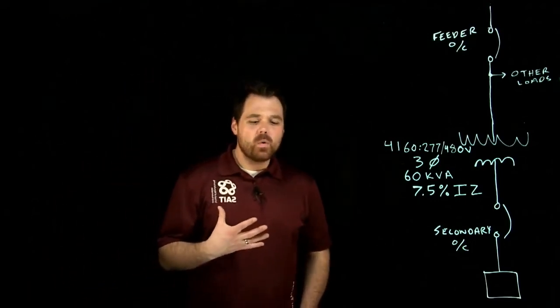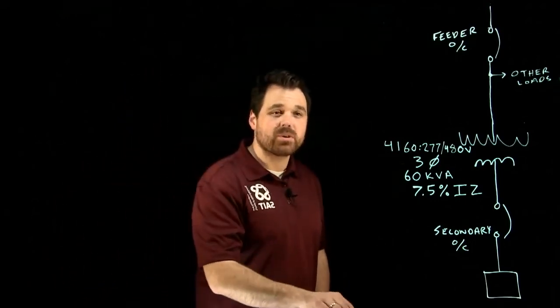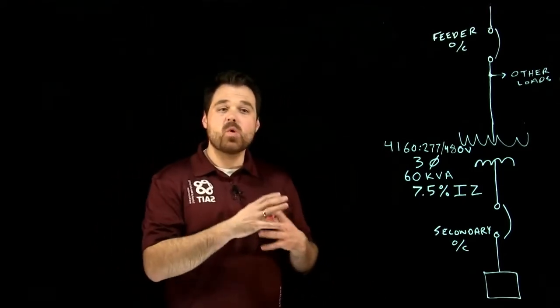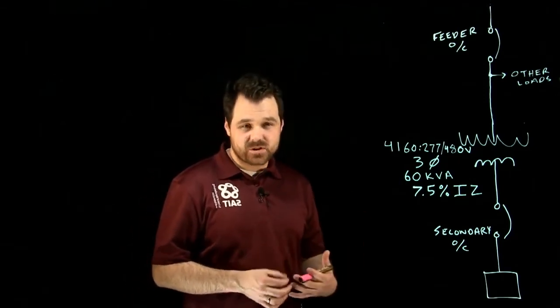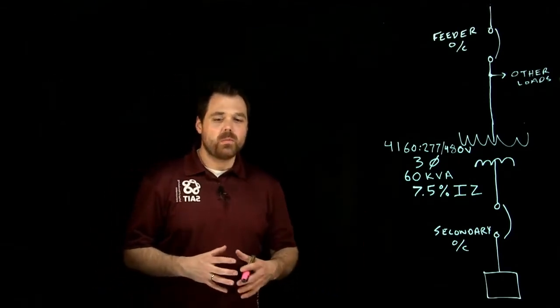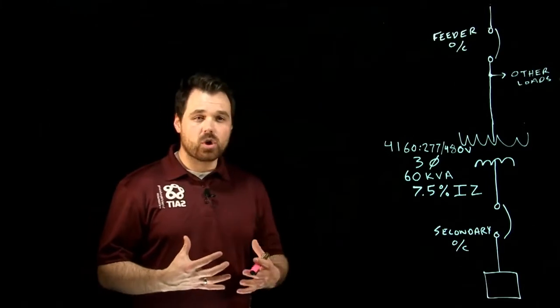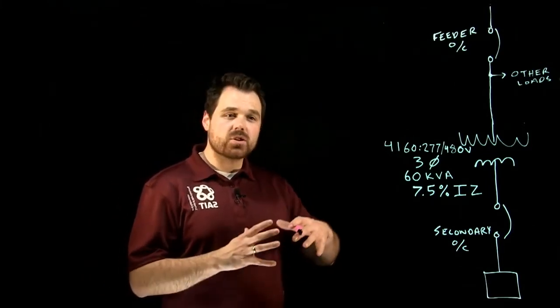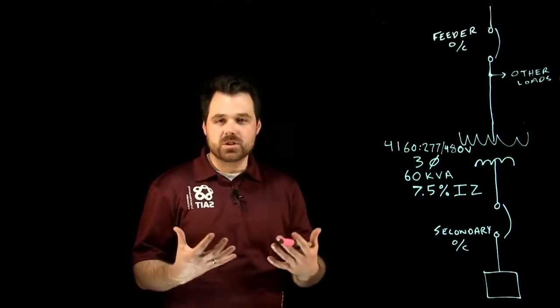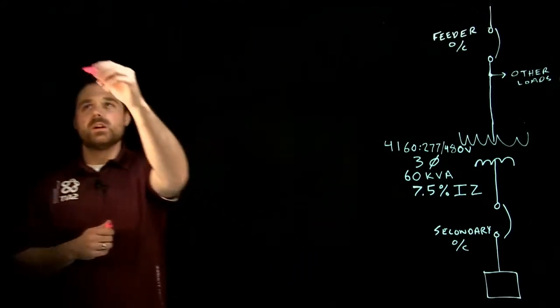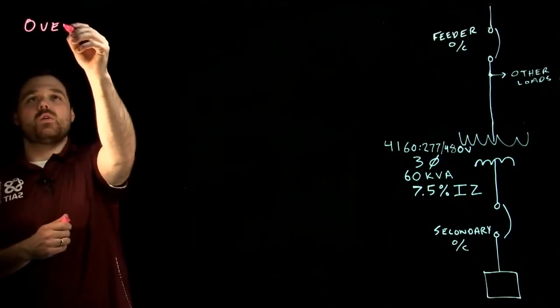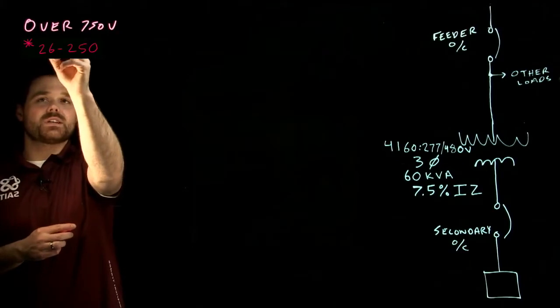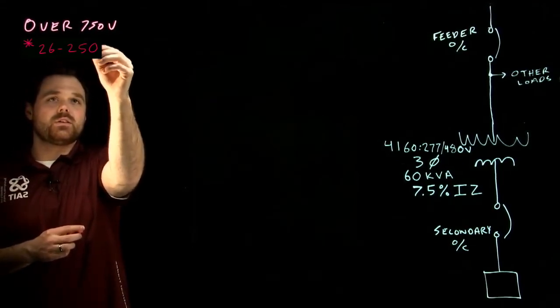Hi. We're here to talk about overcurrent protection for a transformer. More specifically, we're going to talk about overcurrent protection for a transformer over 750 volts. When we're going into the Canadian Electrical Code Section 26, it's important that we're dealing with the right rule to make sure we're applying the right process to a transformer. With a transformer over 750 volts, we are dealing with 26-250.